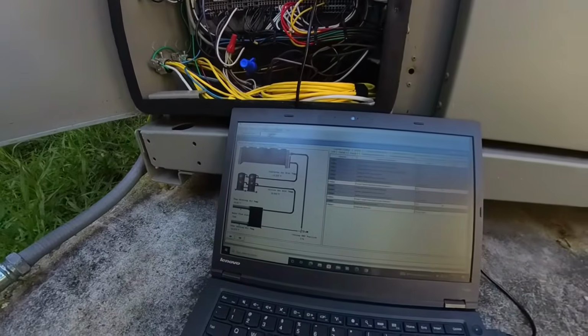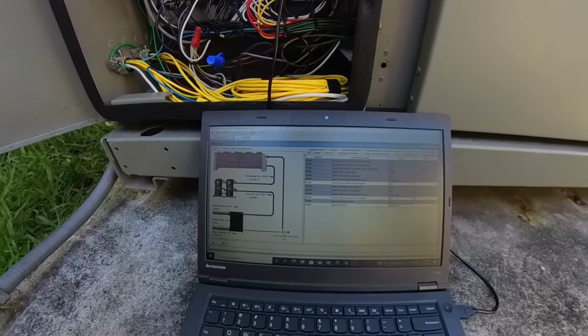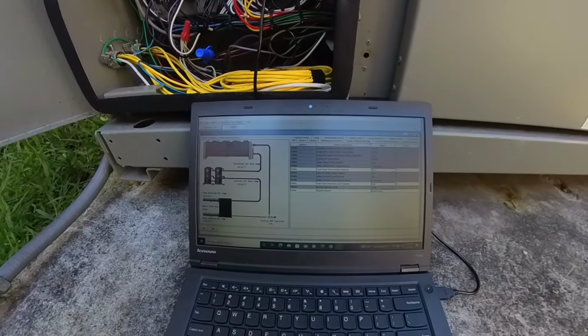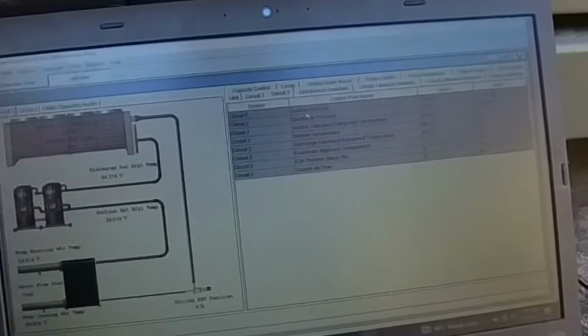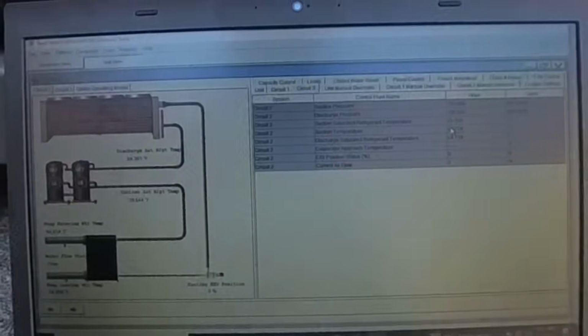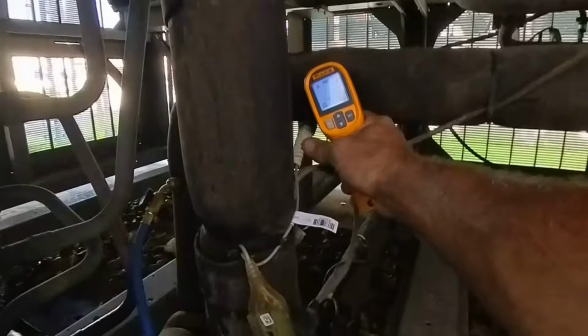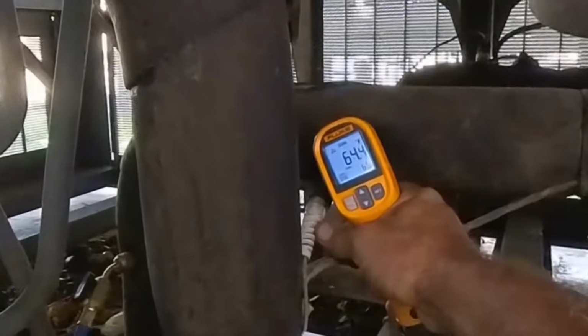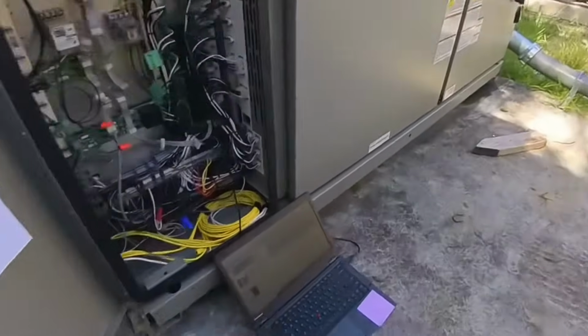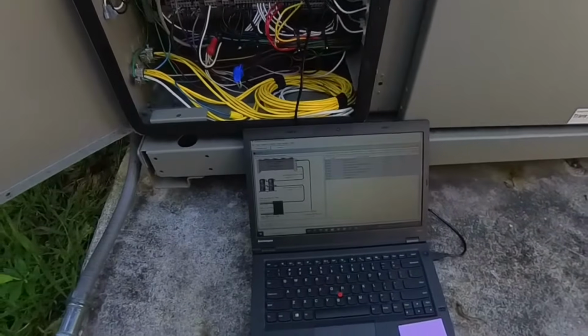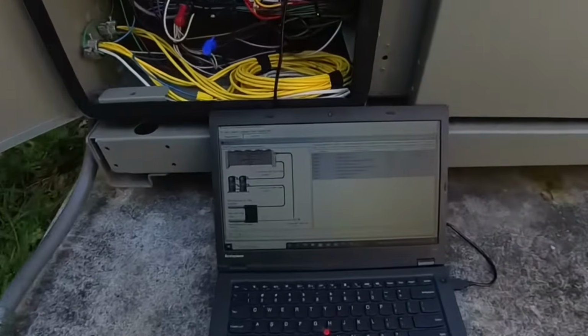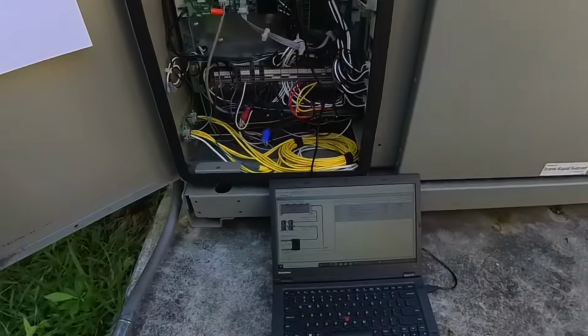We've got our unit view back up here. Our, let's see, circuit 2, suction saturated temp was 65, suction temperature 64, which is probably about right because the chiller's been stopped, and we were about 60 degrees before. Let's get in there. 64.4. All right, we're reading more accurate now. I think we can go ahead and restart this chiller and see what happens.